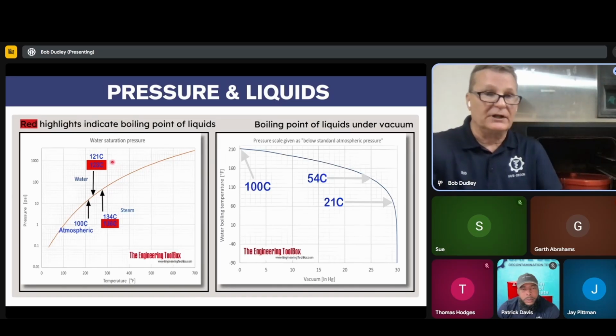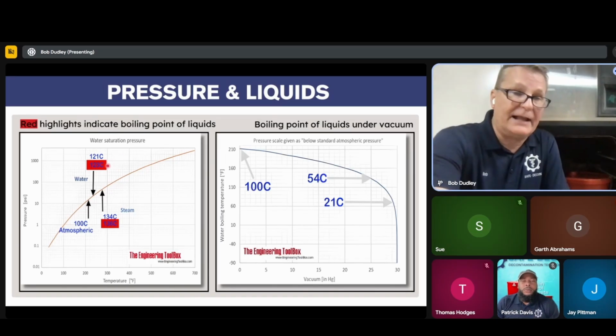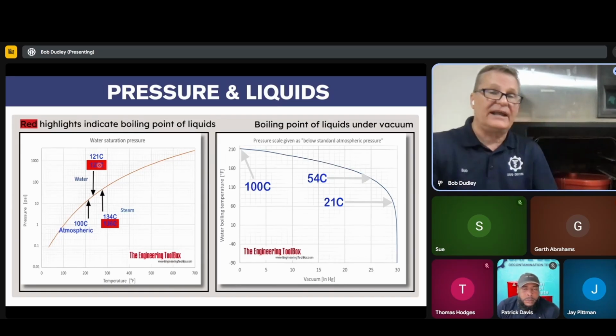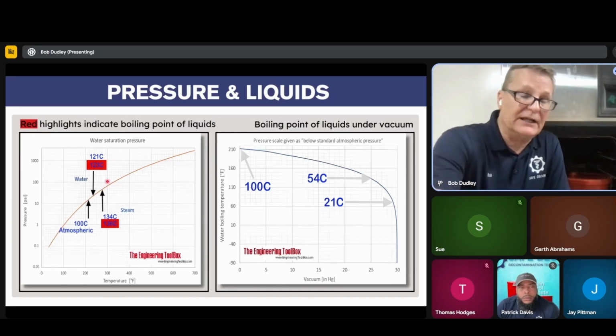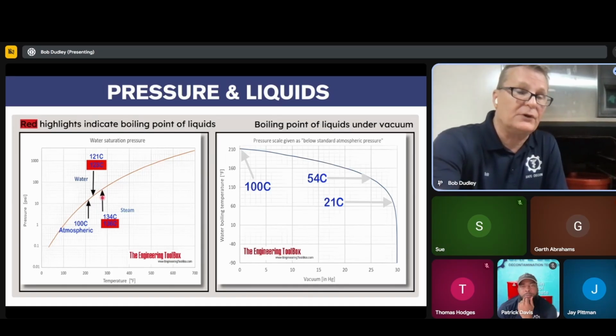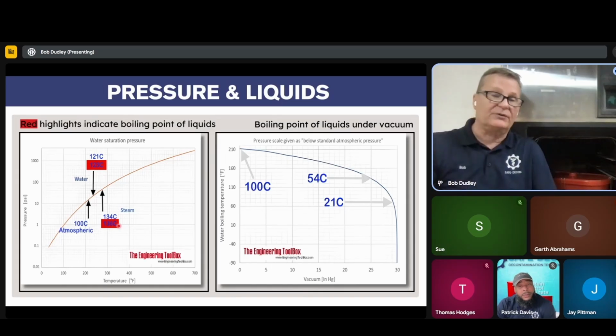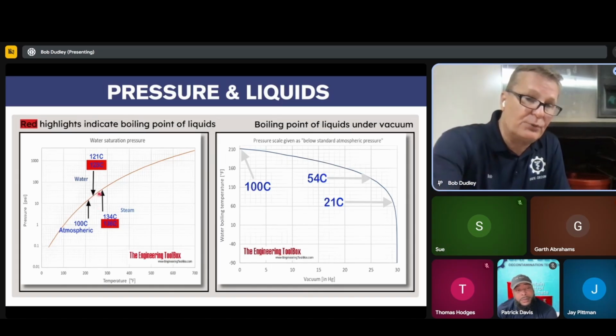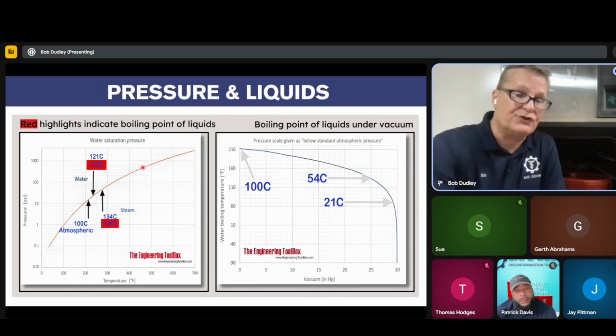And as most of you know, when you run a liquid cycle, boiling is bad. This is where you boil over. So you go, okay, Bob, we're trying to decontaminate, we really want to produce more steam, so we'll just crank up the autoclave. The autoclave is capable of going up to 32 PSI, which equates to 134 C or 274 Fahrenheit. So let's look at what happens here. We're at 134. Your boiling point is now 135.8, or roughly 136 degrees Celsius. So as your pressure increases, your boiling point changes.